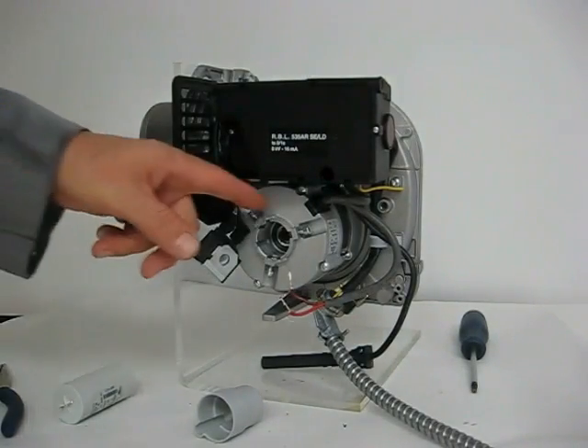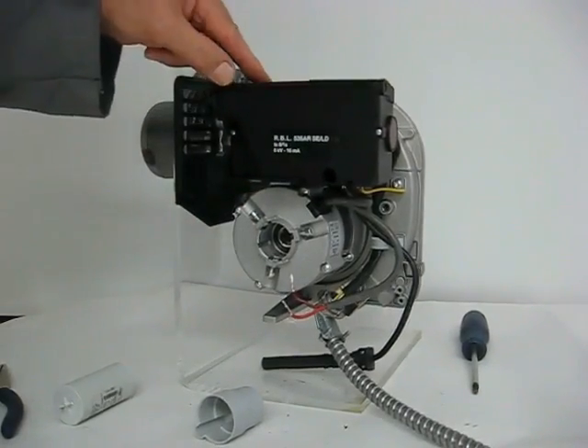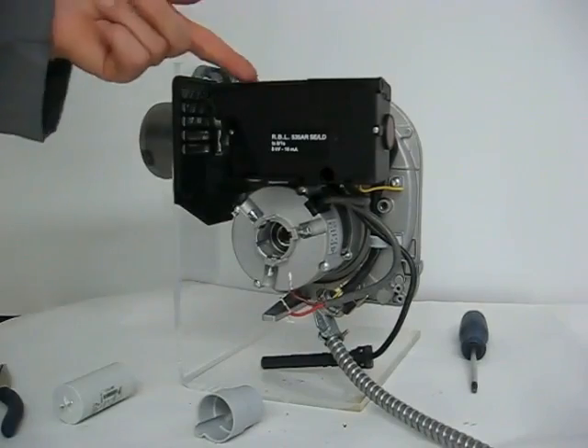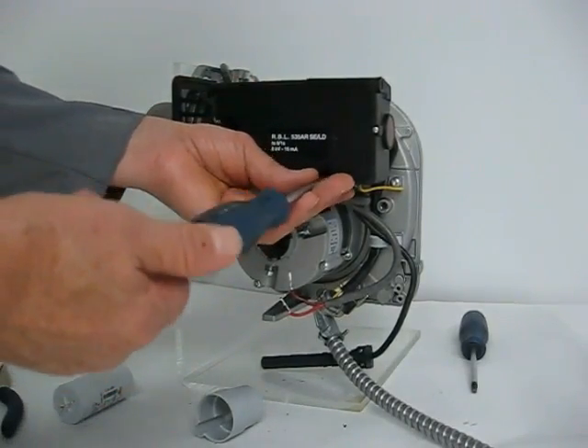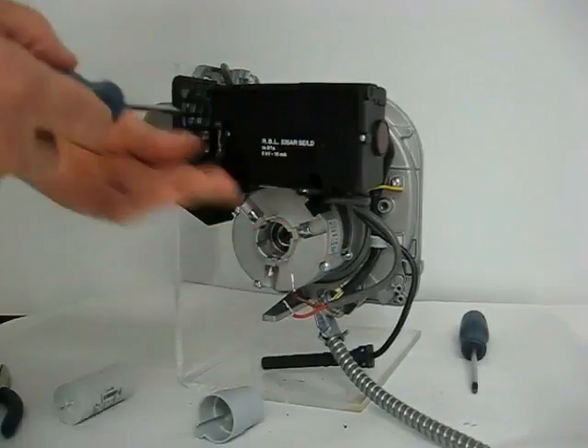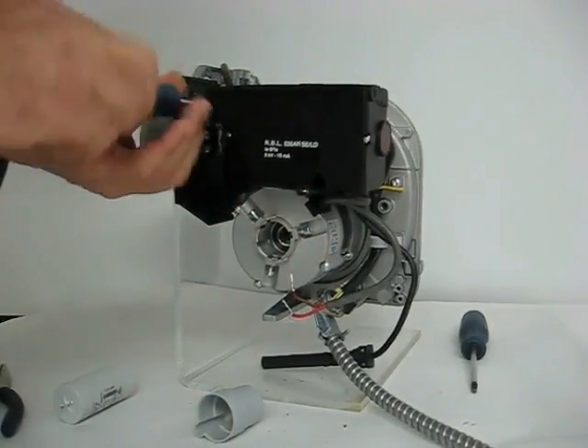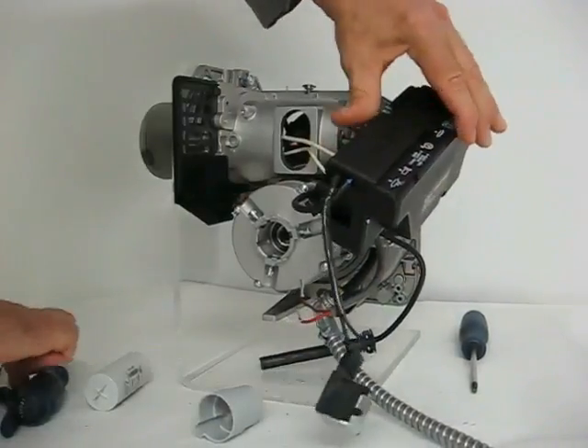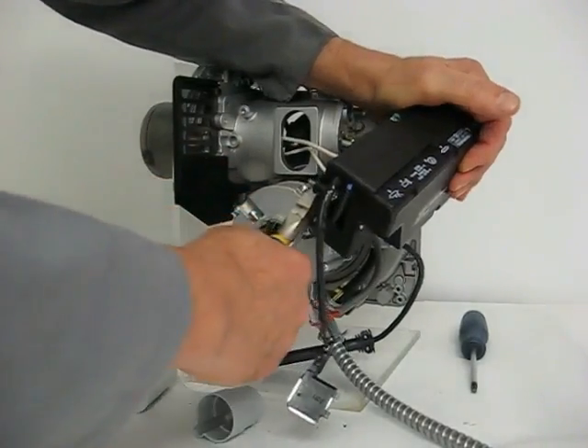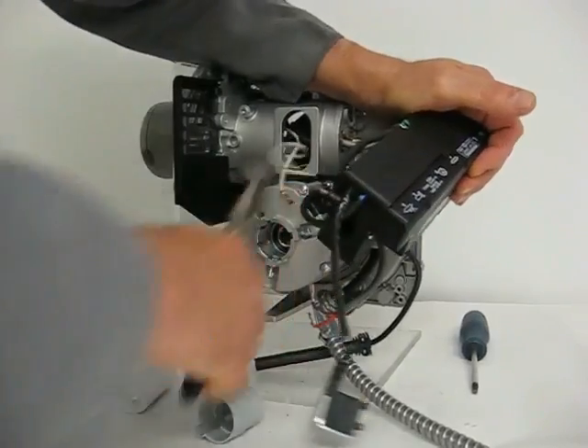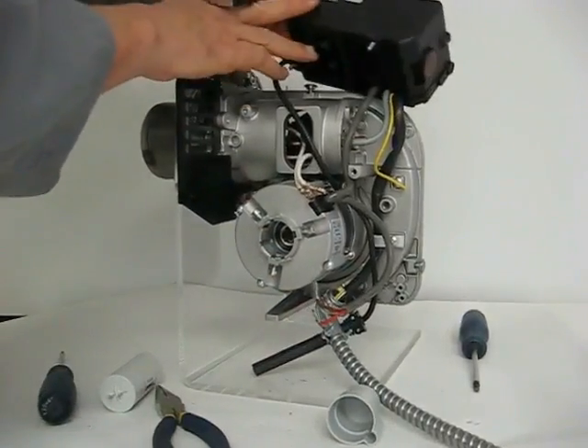To remove the motor, it's easier if we get the flame control box out of the way. You hear a lot of terms for this control: primary control, control box, black box, brain. There's just two screws holding onto the body of the burner. The igniter is internal in this box, so I'll disconnect the ignition wires. This allows us to move that out of the way.